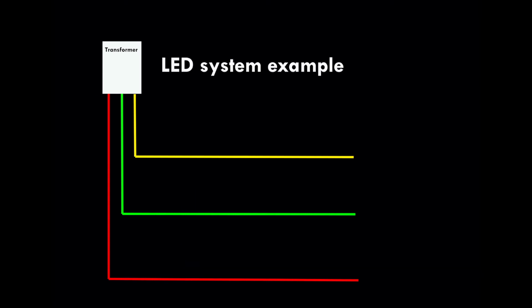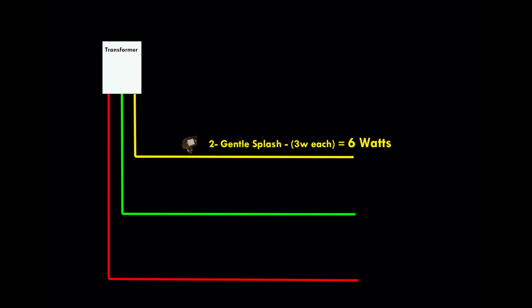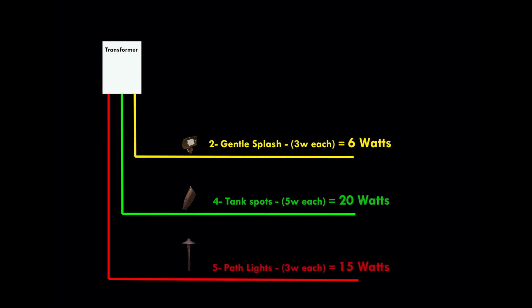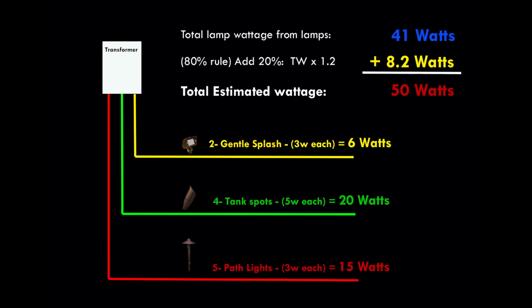Now let's look at the same design example another way. This time we'll be using the much more energy efficient LED lamps. Instead of 40 watts on the yellow run, we'll only be using 6 watts. For the spotlight on the trees, 20 watts instead of 140, and on the pathway lights, 15 watts instead of 100. Add up our total at the top of the page, add 20%, and we have our total estimated watts consumed. The choices for the LED installation could be either our 75-watt transformer or even our 300-watt transformer if you plan to add on at a later date.